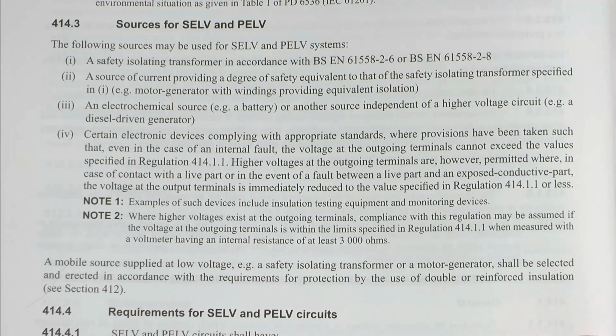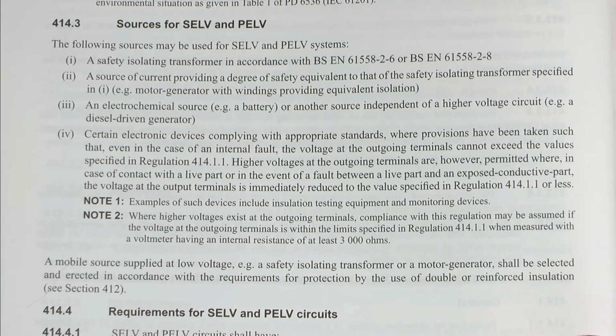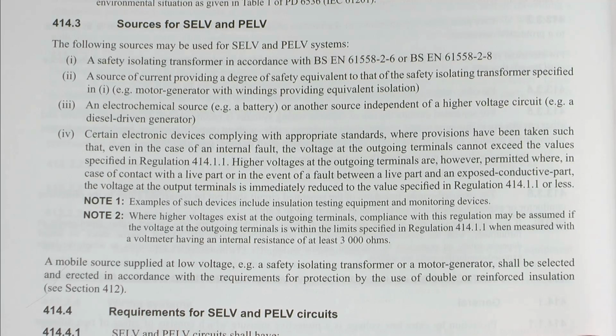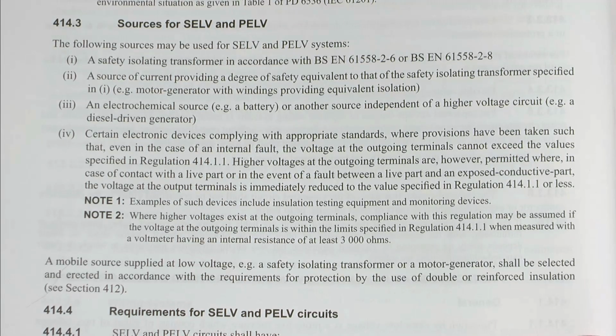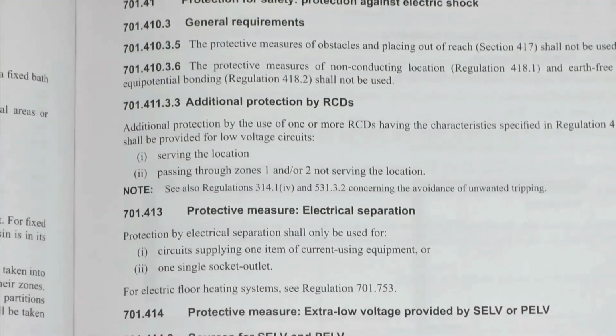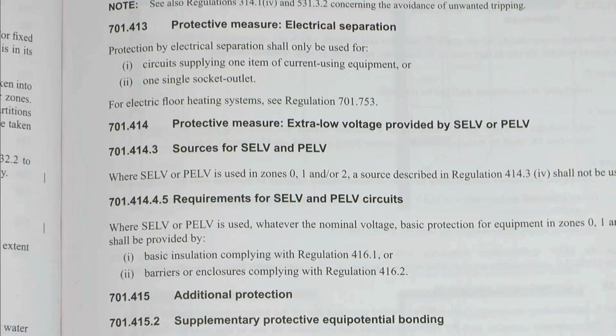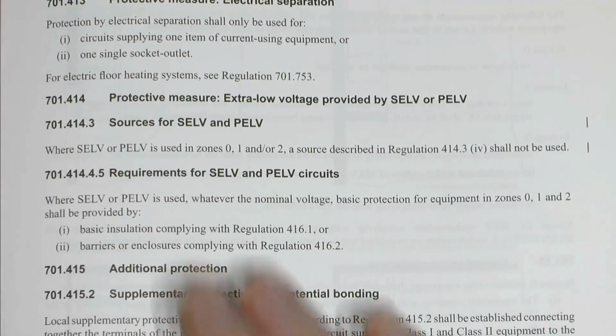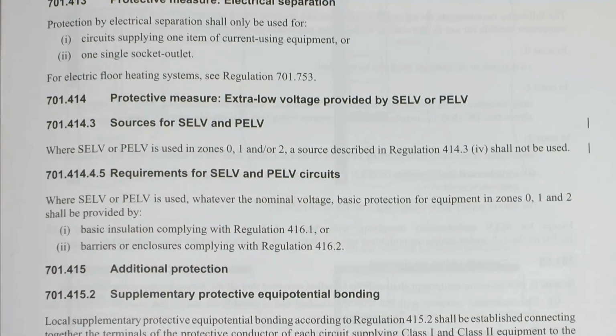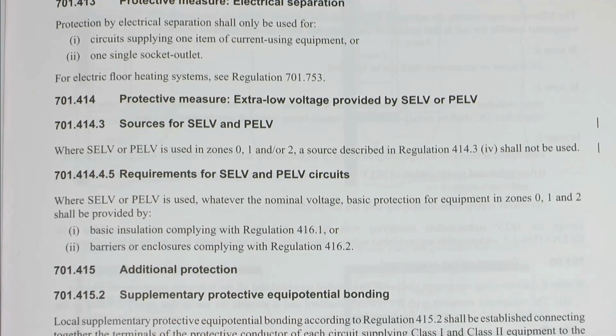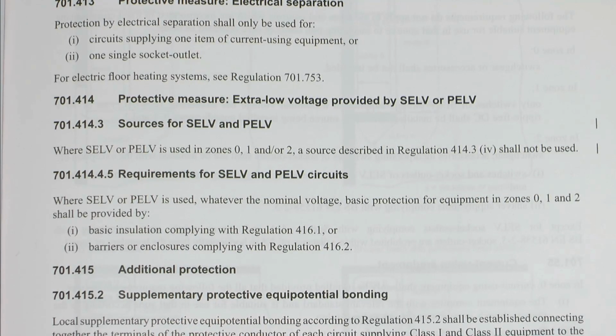Some of these are marked as sort of SELV equivalent and various things. So essentially if you want to use SELV power, you've got to use one of the other things, which is probably what's listed there. So a safety isolating transformer, or one of the other two items there, and not item 4. And that applies to areas with a bath or shower, and it also applies to several other chapters in here. So it's just a question of that it's not to be used in indent 4, but of course you can use indents 1, 2 and 3.